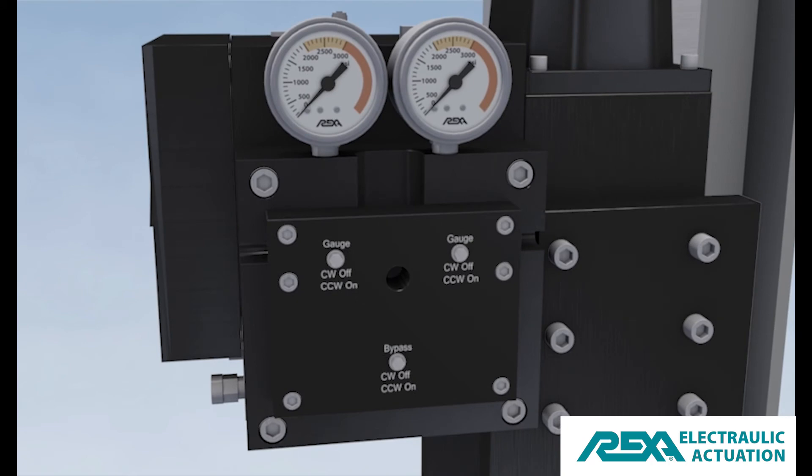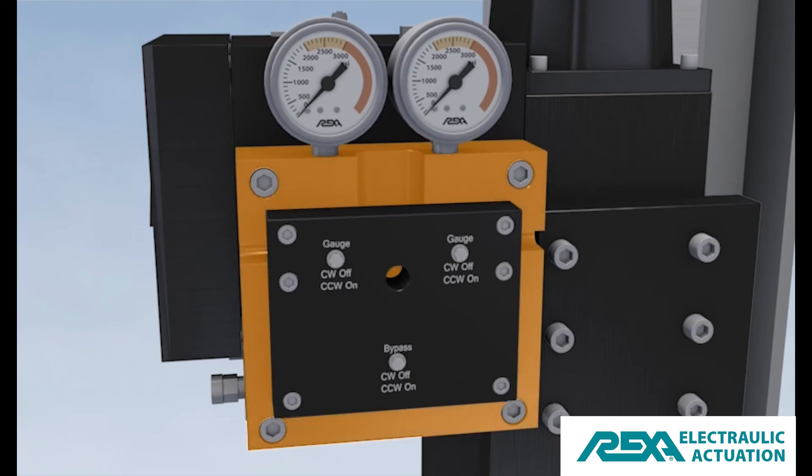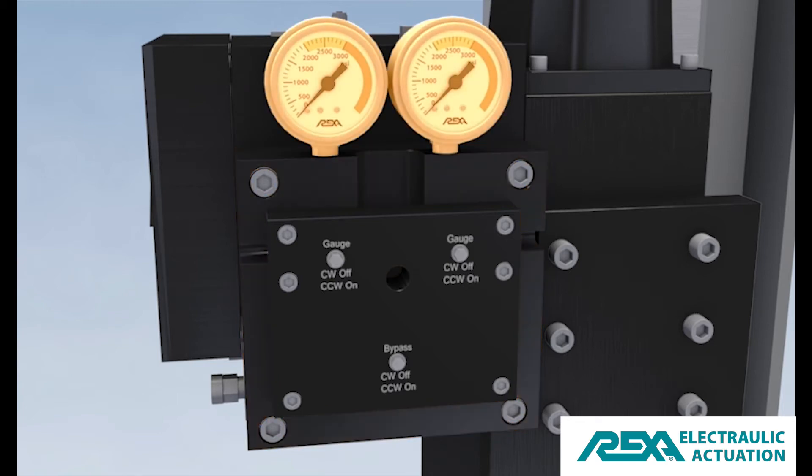The powertrain components are fastened to a manifold. The manifold fastens to the power module block and contains two pressure gauges that monitor the extend and retract pressures. The gauges are used for troubleshooting and observation purposes and are isolated during normal operation to lengthen their life.